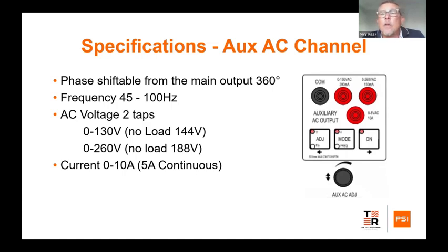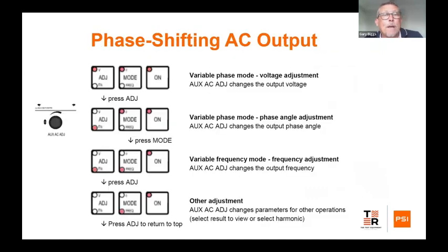In addition, on that channel, we can give you current up to 10 amps, and we can give you current up to 5 amps continuously. Obviously, on the 10 amps, there is a duty cycle, but relays normally have trip times of 5 to 10 seconds at the most.